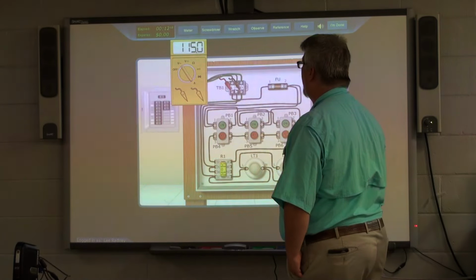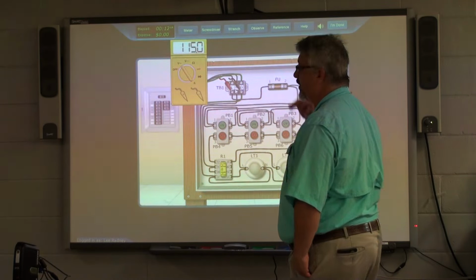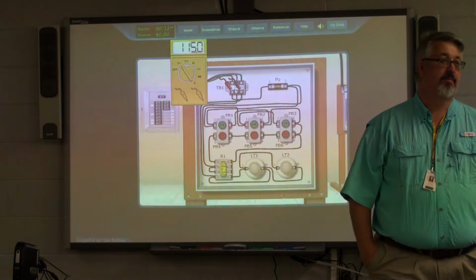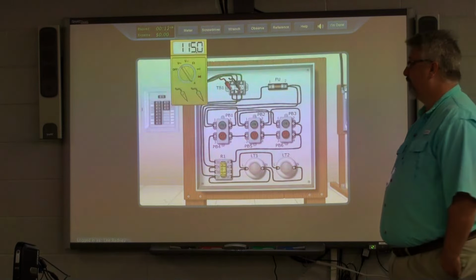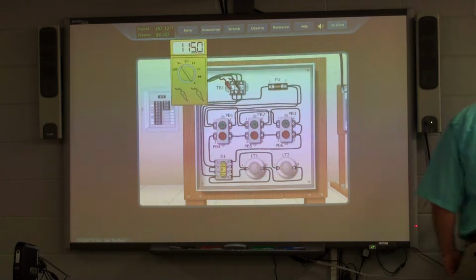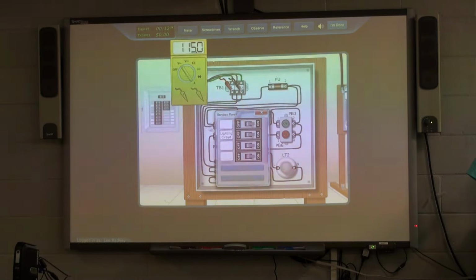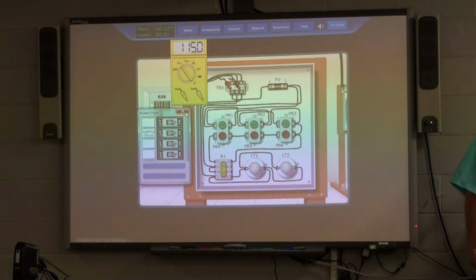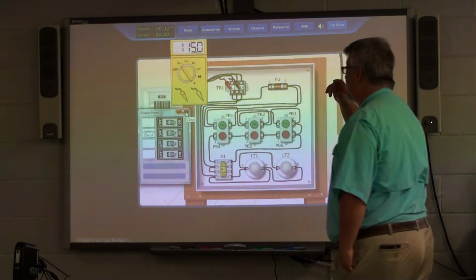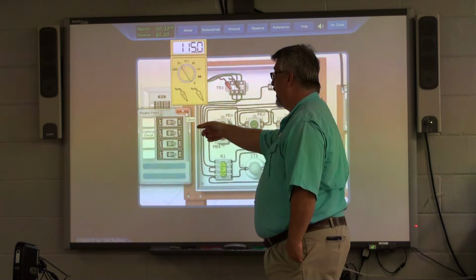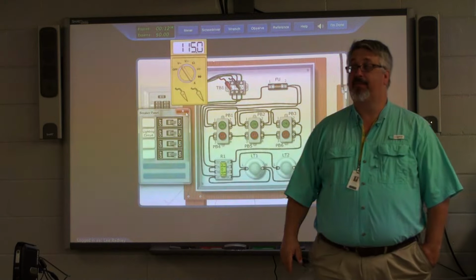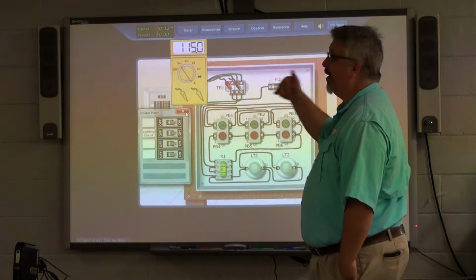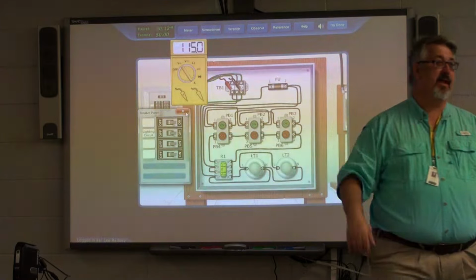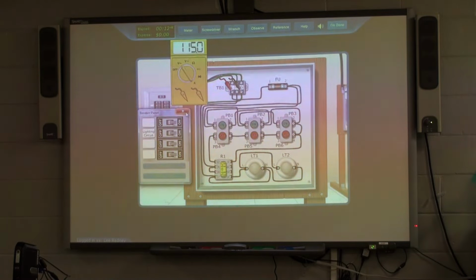What can happen to this circuit to potentially kill voltage at that terminal block? We could lose power to the power box, and that could happen a couple of ways. We go over here to the breaker panel and shut it off—sure enough, we lose power. Or a blown fuse—well, not there, the fuse is beyond it. Now we could trip the breaker, and that would do it. Or we could have a broken wire between wherever our source is and that terminal block. So there's a few things that could happen.